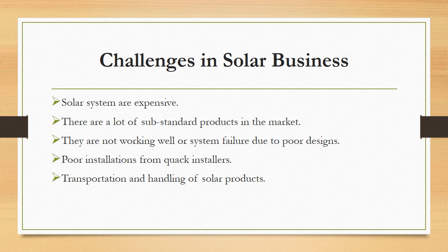Another issue is that some energy auditors—or people called installers who did the load analysis—if they didn't do the analysis properly, it can make the system fail. Maybe the correct calculation comes to 3.5 kVA, but since the person doesn't have a good understanding, or wants to reduce cost, they size the system to something like 2 kVA. When you install a 2 kVA system for a 3.5 kVA load of appliances, the system will not work well and will start failing because of the poor design. So these are other challenges.